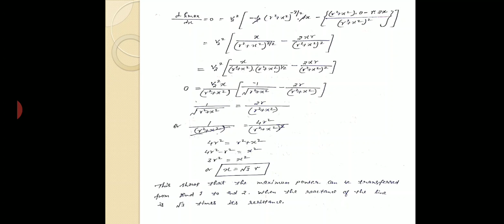Okay. Now here we have one numerical also, a very important numerical, and the concept of two-port network is also used here. The ABCD constants of a nominal pi network representing a three-phase transmission line are A equal to D equal to 0.97 angle 0.6, B equal to 60 angle 70 degree, and C equal to 0.001 angle 90 degree. Find the steady state stability limit if both the sending end and receiving end voltages are held constant at 132 kV. Part A with the ABCD constants as given. Part B with the shunt admittance neglected, and C with both the series resistance and shunt admittance neglected.